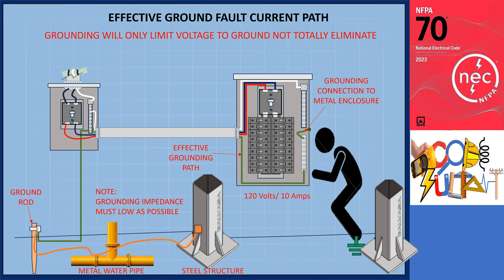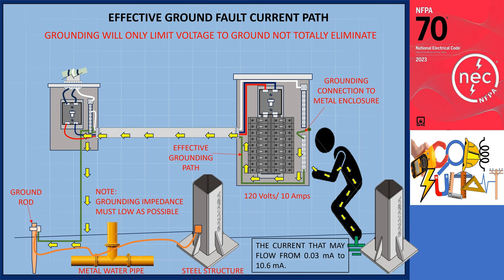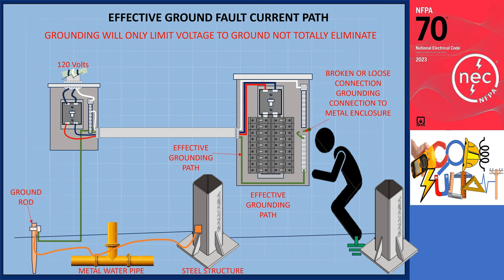In a scenario with a 120-volt, 10-ampere power source, current follows the path of least resistance through the equipment grounding conductor. This can result in personnel being exposed to a potential of 3.19 volts on the conductive surface of the equipment case — at which level, current through a person may range from 0.03 to 10.6 milliamperes. However, with a broken or loose grounding connection to the metal enclosure, the person could be exposed to 116.81 volts, which can be harmless or lethal.